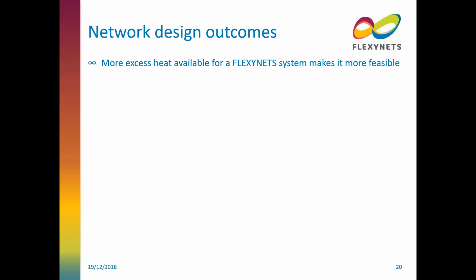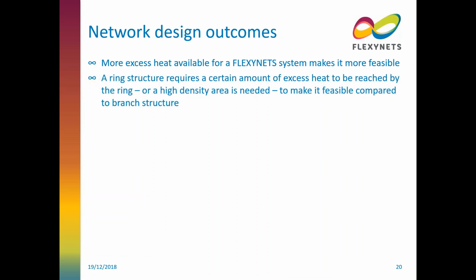So in general, one key outcome is that the feasibility of FLEXYNETS really depends on the ability to use excess heat, and there will be a lot more excess heat potential at lower temperatures than high temperature. Also, a ring structure requires a certain amount of excess heat or very high density area to be reached in order to make it feasible compared to a branch structure, which might be more common.